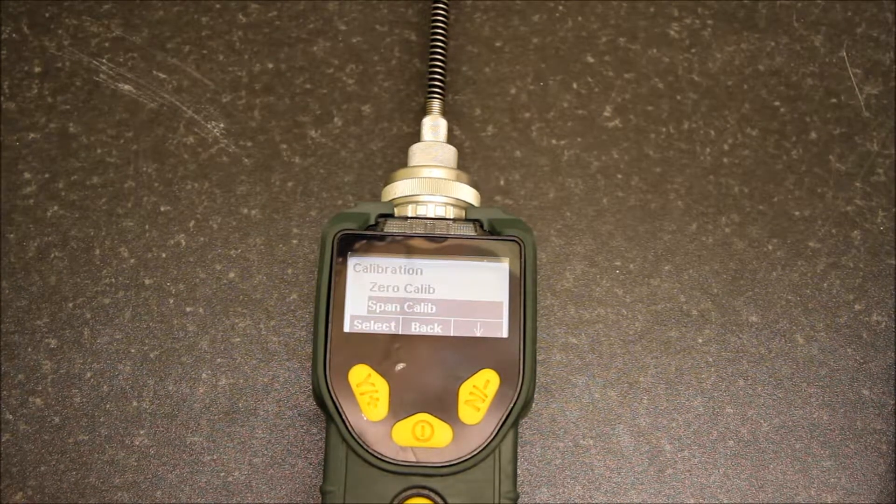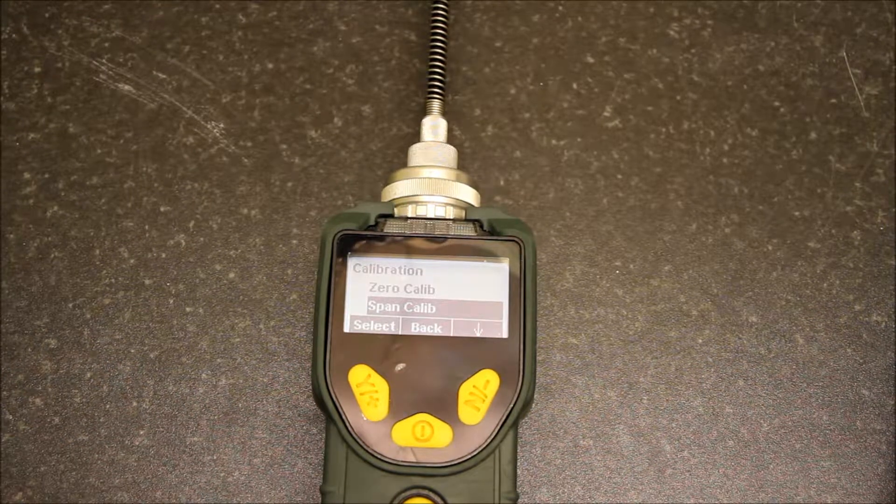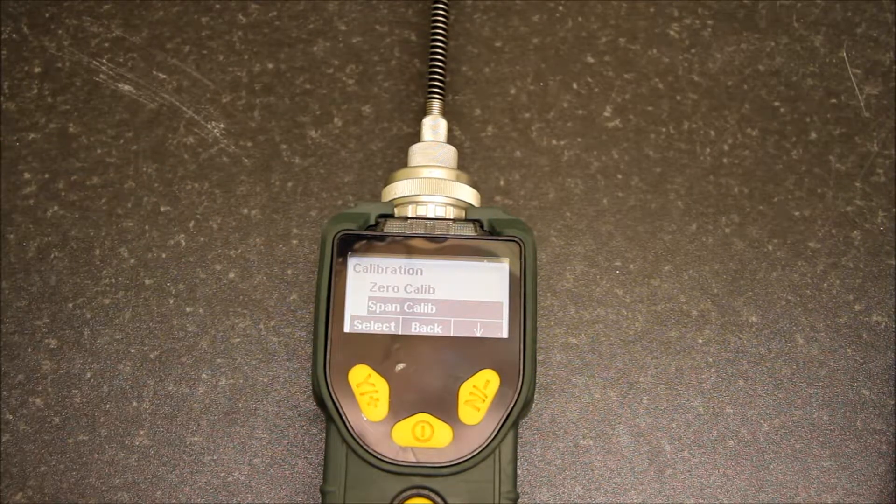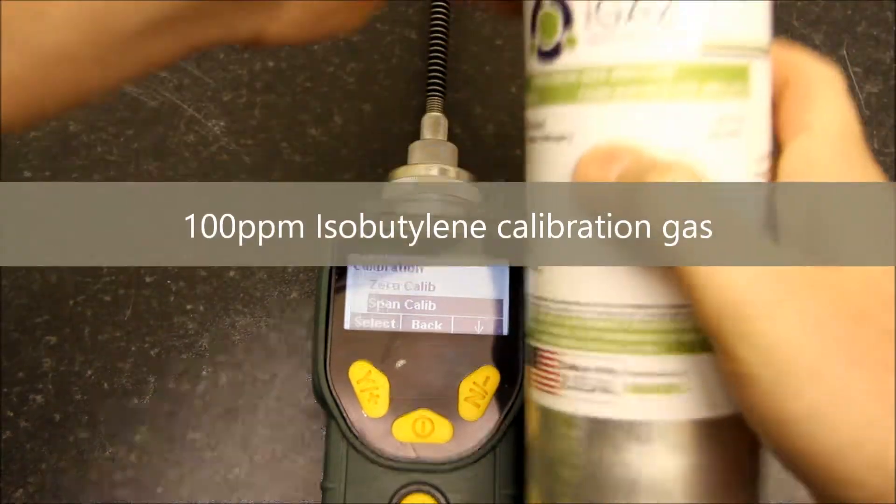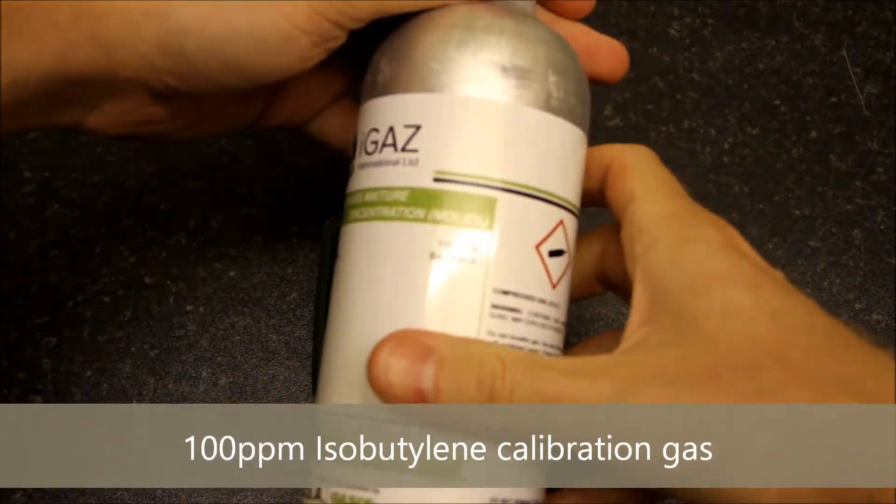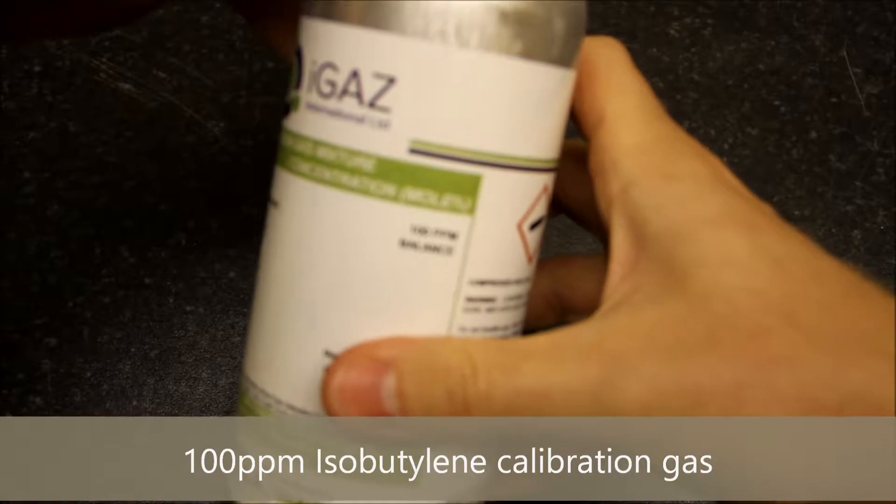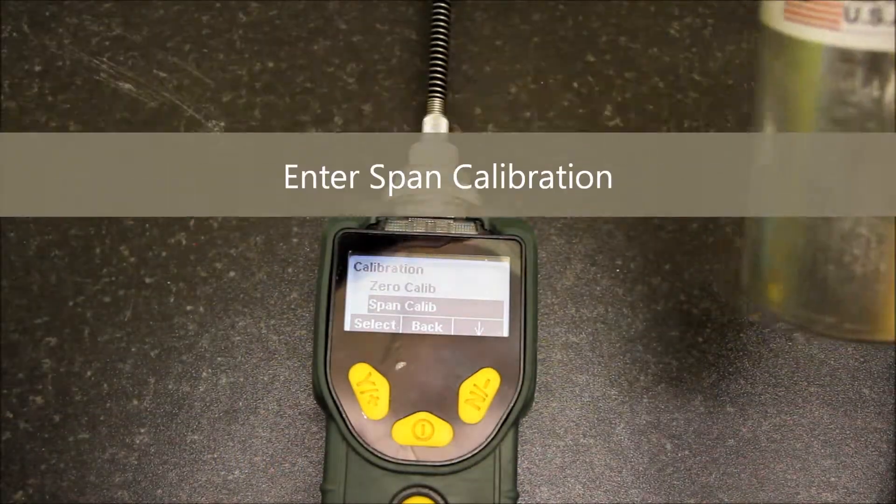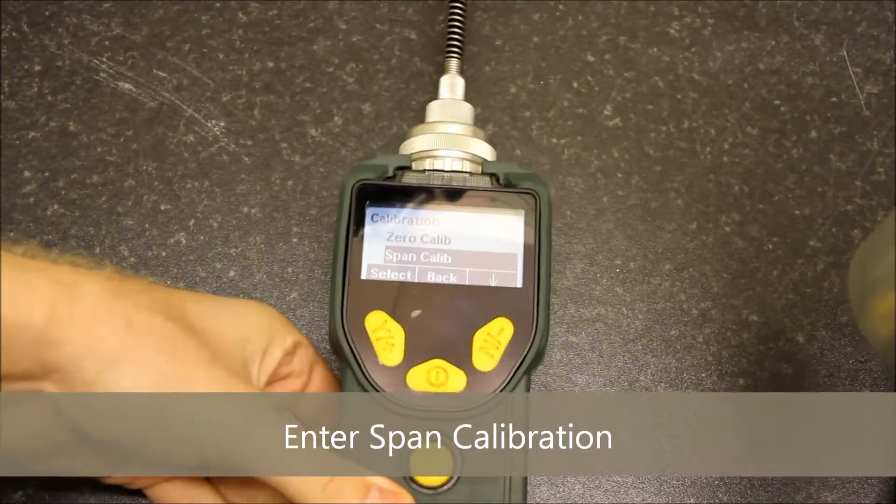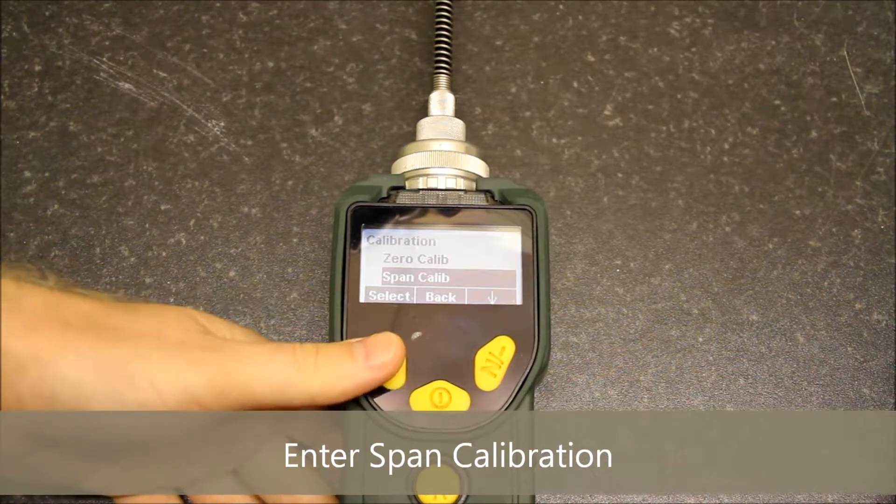The unit is now zeroed, reading 0.0 ppm, and it's now gone into span calibration next in the list. We're going to be using 100 ppm isobutylene gas here. So 100 ppm isobutylene gas, and we are going to drop into the span calibration.